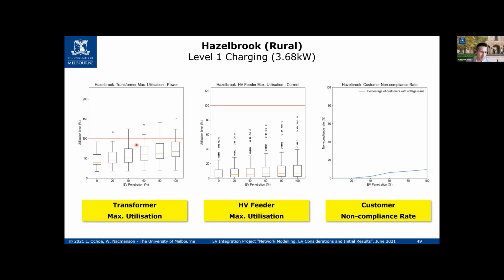So already with 40% electric vehicle penetration with level 1 charging, a rural feeder, in this case Hazelbrook, can be compromised, particularly the transformers. Some transformers will be compromised. In terms of voltages as well, we'll see problems at 40% penetration, and that's not good. The high voltage conductor in this case doesn't have problems.